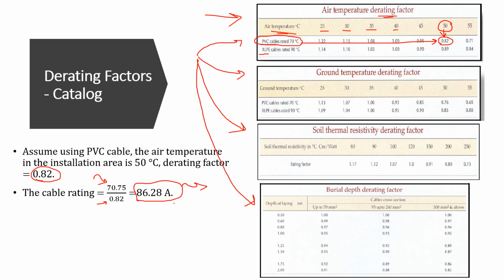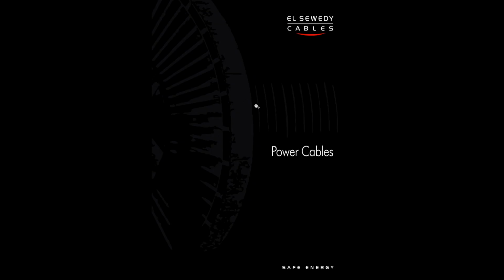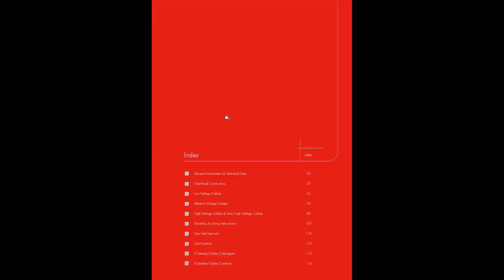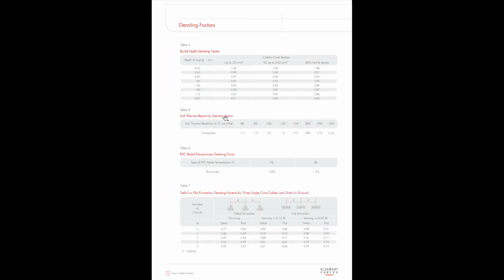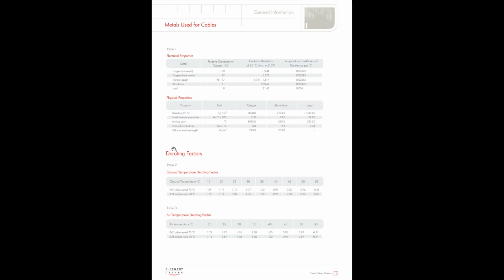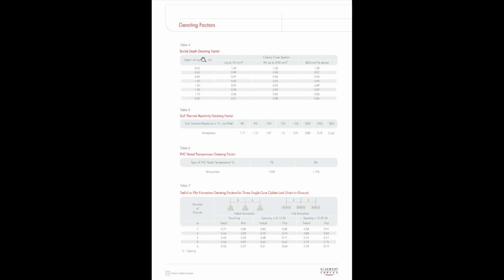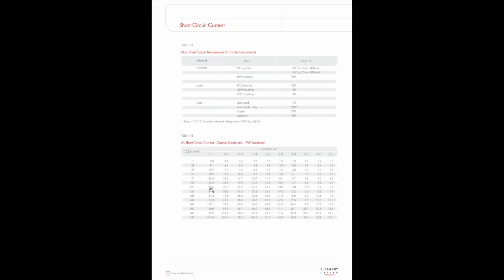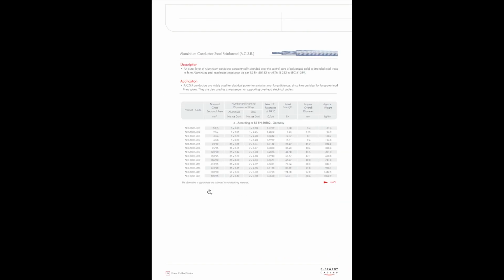Okay, so now I have opened the El Sewedy power cables catalog. Now we would like to search for a cable which can help us in this problem. As you can see, inside the catalog you will find many data, for example the derating factor which we just discussed. You can find the ground derating factor, since if the cable is buried under the ground, then it has a derating factor depending on the ground temperature. Also, we have a depth derating factor, the parallel depth of the cable itself, and the soil thermal resistivity derating factor depending on the soil resistivity itself, and so on. Also there is the cable formation, which we discussed in a previous lesson. So now let's go and search for some cable.